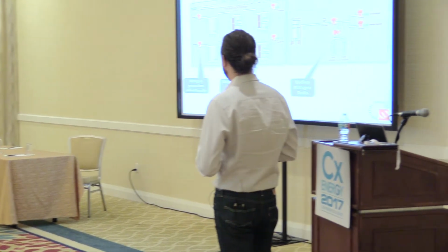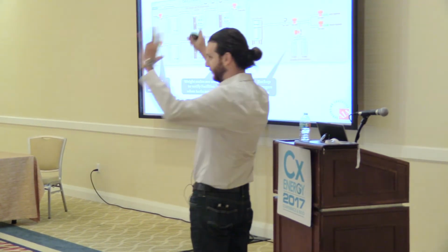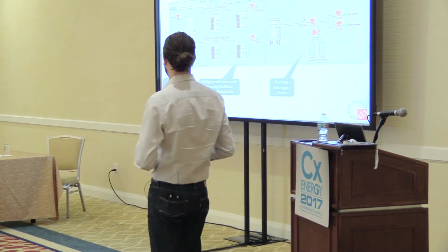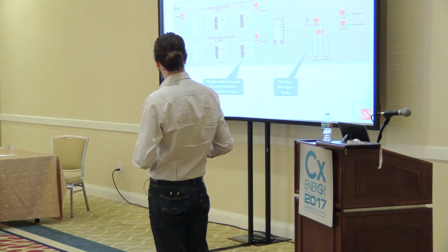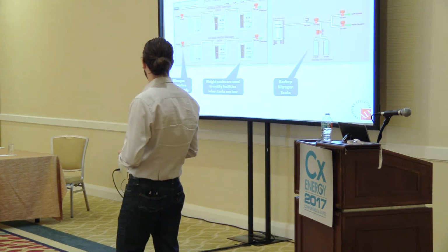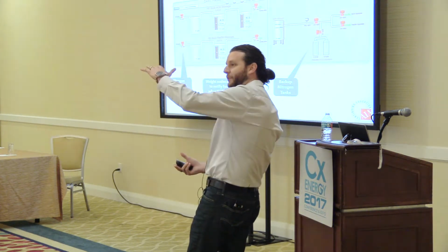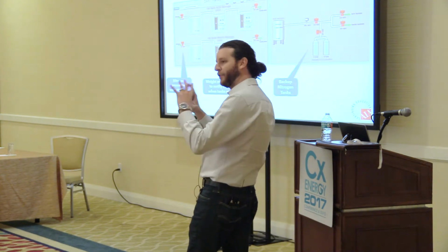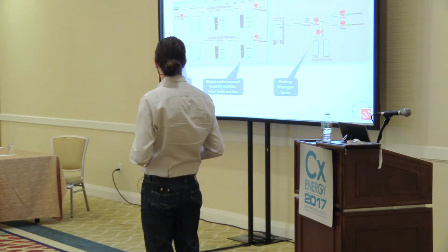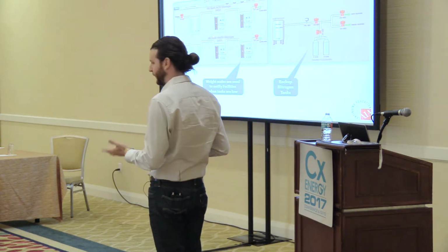So the way it worked, and I just want to talk through it and hit some commissioning lessons learned, is they used nitrogen. There's a bulk nitrogen tank out in the yard, liquid nitrogen, that goes through a vaporizer to gas. That gas is then pumped into the solvent system. Nitrogen pressurizes these tanks, the tanks I showed you on the slide before, and they roll them onto these weight scales. The weight scales are then calculated to the tank level. They say, if I'm at 15 pounds, based on the volume of the scale and the density of the liquid, I'm at this level in the tank. And these valves are used to control the tank levels, so they open and close based on the demand in the space.